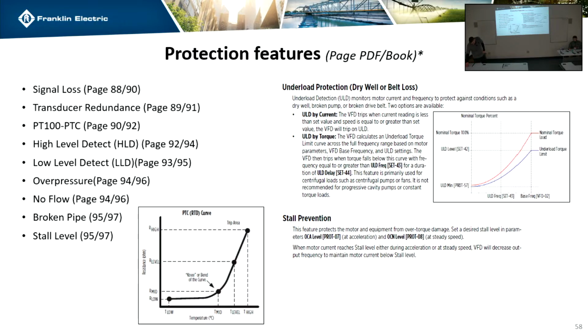Yeah, low level is just a trip. Okay. Overpressure is specific to direct PID. Basically, if the drive is not operating or if the pressure is way over the set point and the drive can't do anything to combat it, it's just going to start flashing overpressure at you, and it will eventually shut down. If you have the PID set up with boost, the overpressure has to get past your boost setting, and if it does, the drive will instantly go to sleep, so it doesn't keep overpressurizing the system.